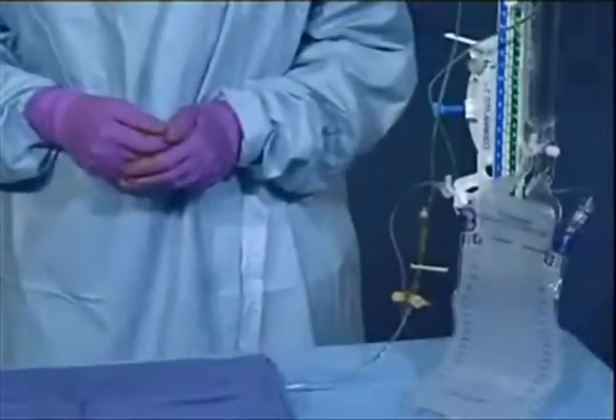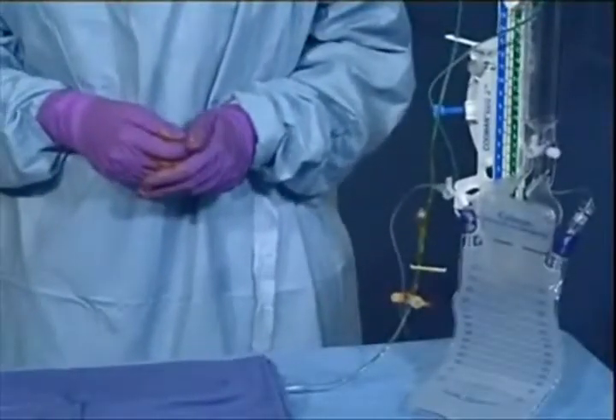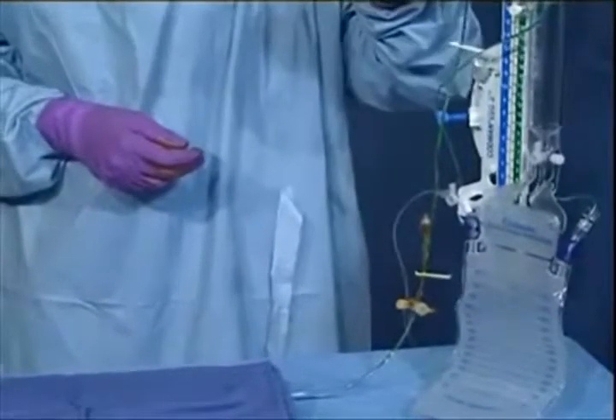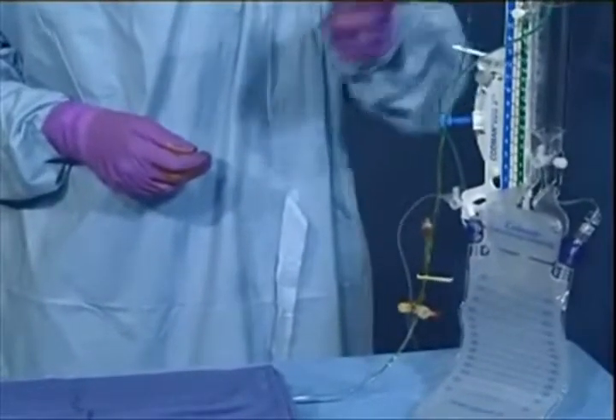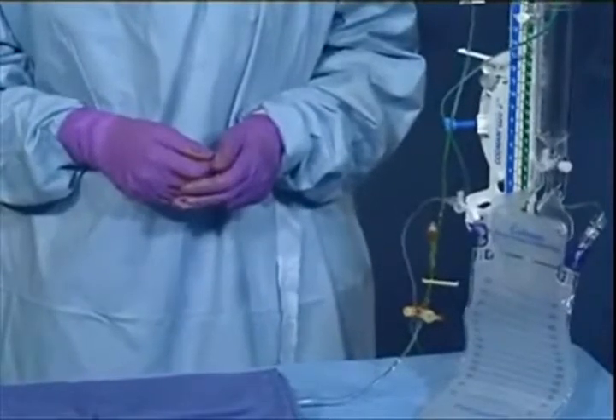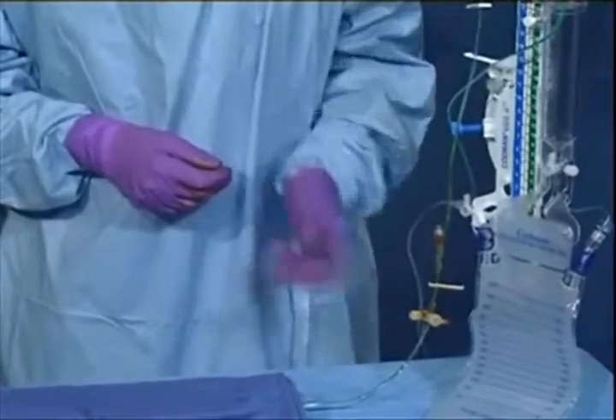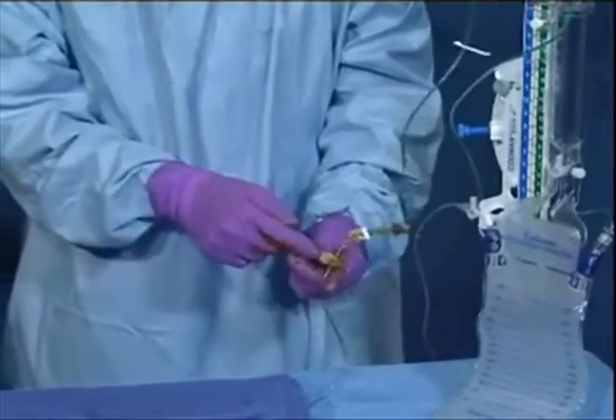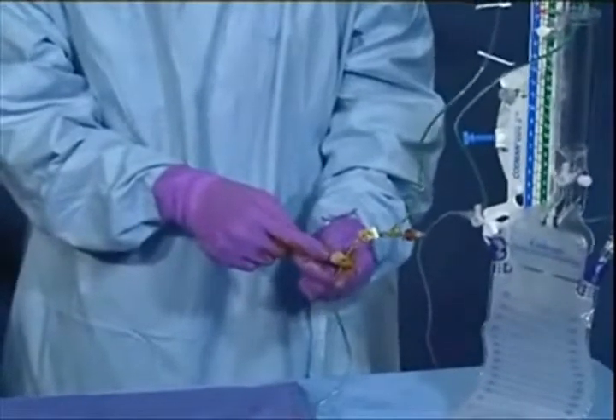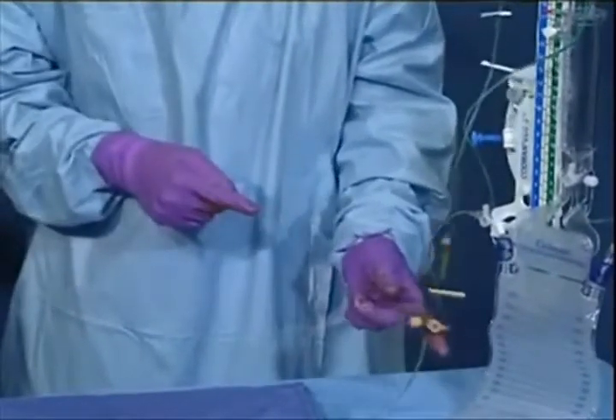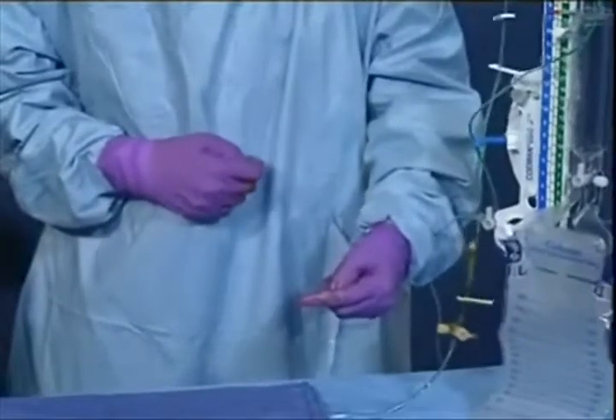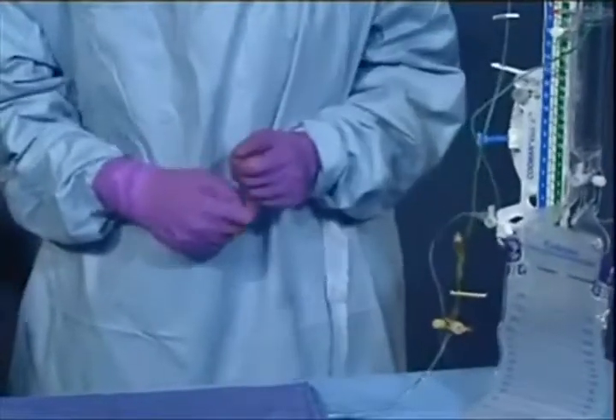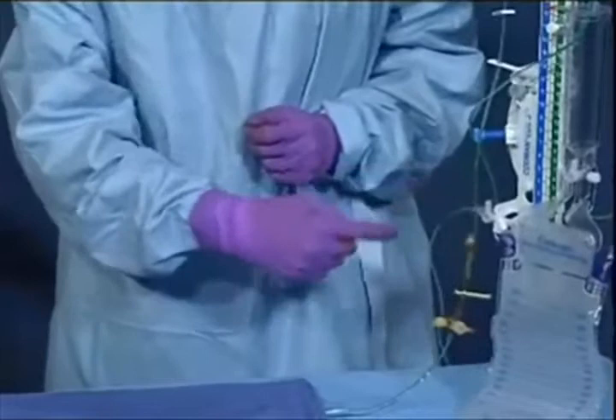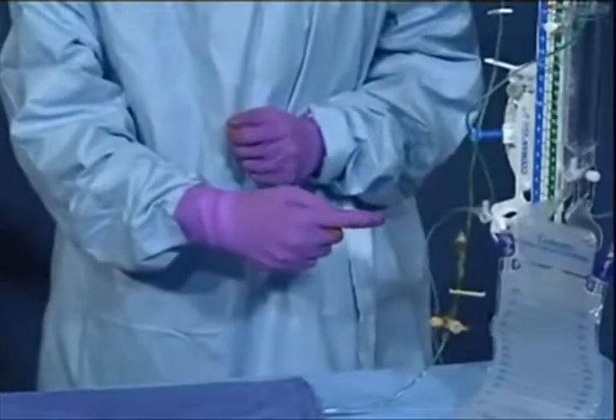You notice that the stopcock is suspended in mid-air, and we do that simply by hanging the tubing over the pole, and we prepare this as best as we can with the iodine solution. You notice just below the rubber port is a 3-way stopcock. In our system, the portion of the stopcock that moves in this direction is towards the patient, and the tubing from the stopcock going in this direction is towards the transducer.